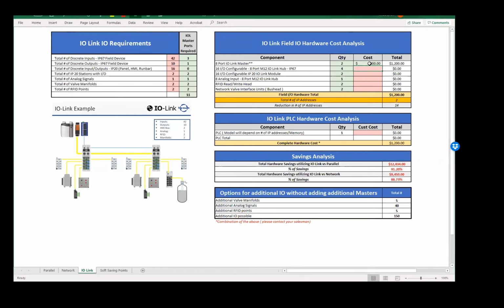Okay. So now that's our only IO-Link enabled device per se. Now we're going to go to IO-Link hardware that connects to that master. And when I say IO-Link device, I mean one that is able to communicate with that upper level network. That's right. The rest will be dedicated IO-Link. Perfect. So we go to a 16 IO configurable block. Mm-hmm. So to handle the inputs and outputs, we need a total of 4 of those. And we'll say those are $200.